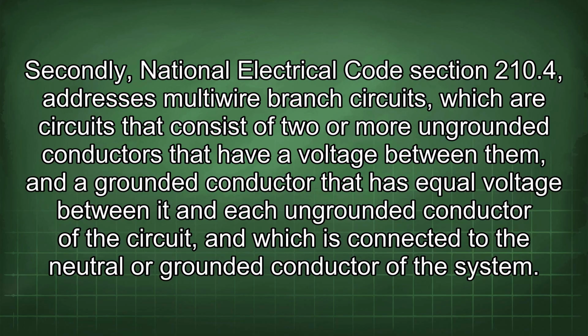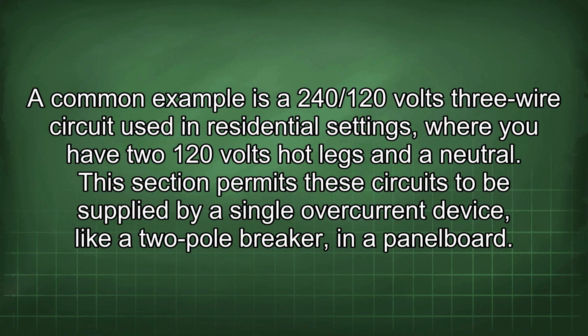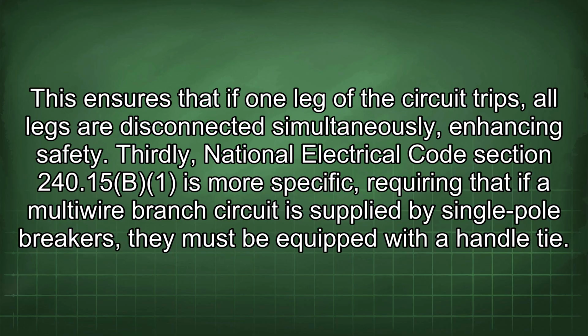Secondly, National Electrical Code Section 210.4 addresses multi-wire branch circuits, which are circuits that consist of two or more ungrounded conductors that have a voltage between them, and a grounded conductor that has equal voltage between it and each ungrounded conductor of the circuit, and which is connected to the neutral or grounded conductor of the system. A common example is a 240/120 volt 3-wire circuit used in residential settings where you have two 120 volt hot legs and a neutral. This section permits these circuits to be supplied by a single overcurrent device, like a two-pole breaker, in a panel board. This ensures that if one leg of the circuit trips, all legs are disconnected simultaneously, enhancing safety.